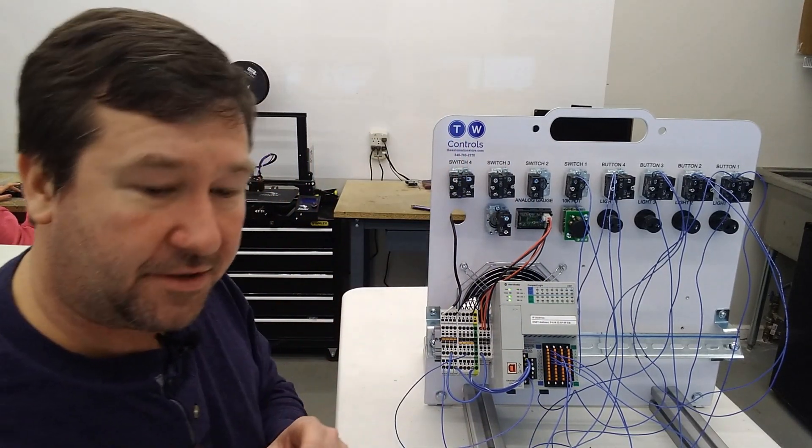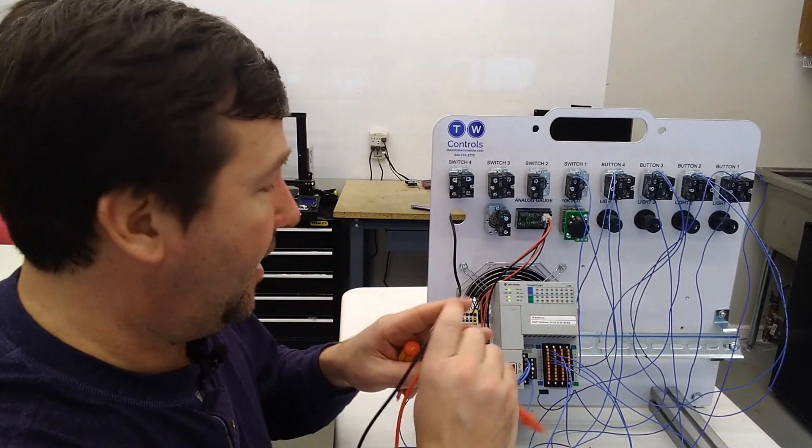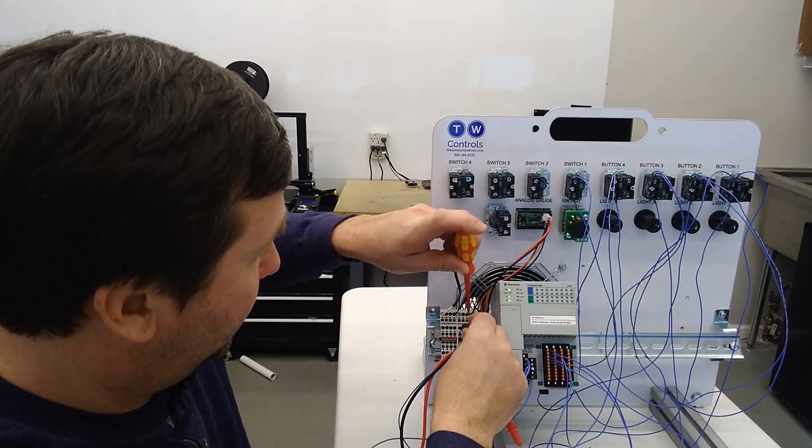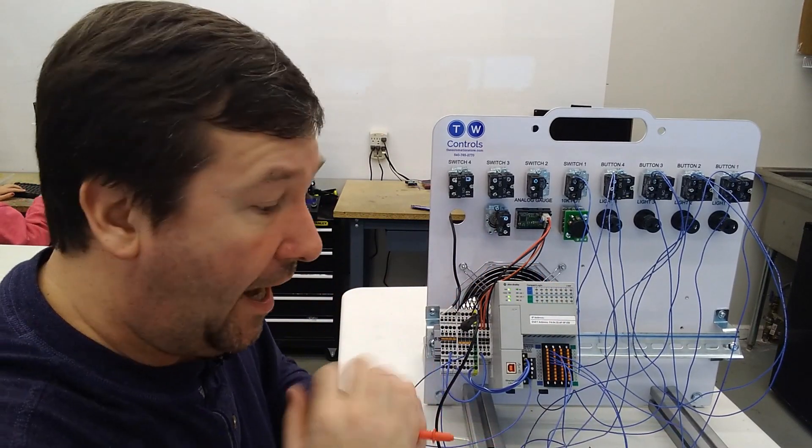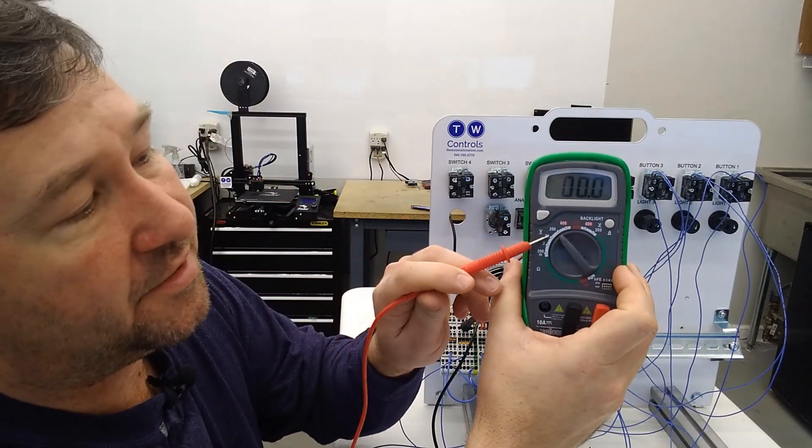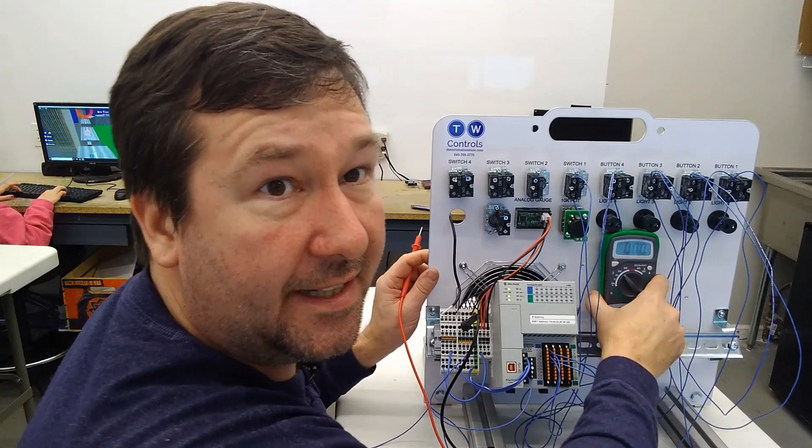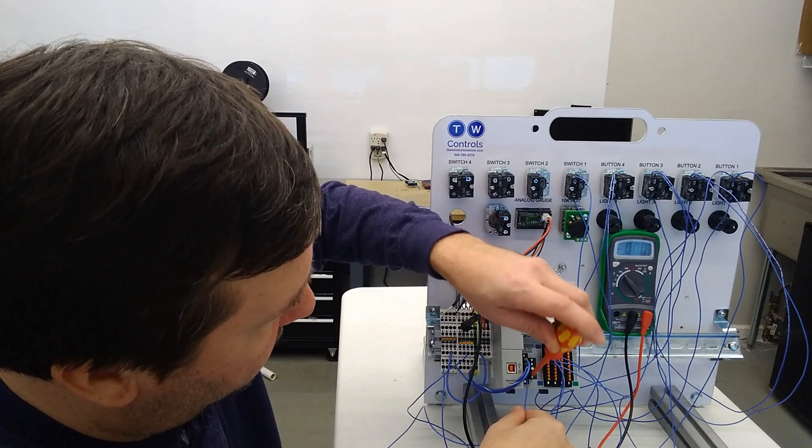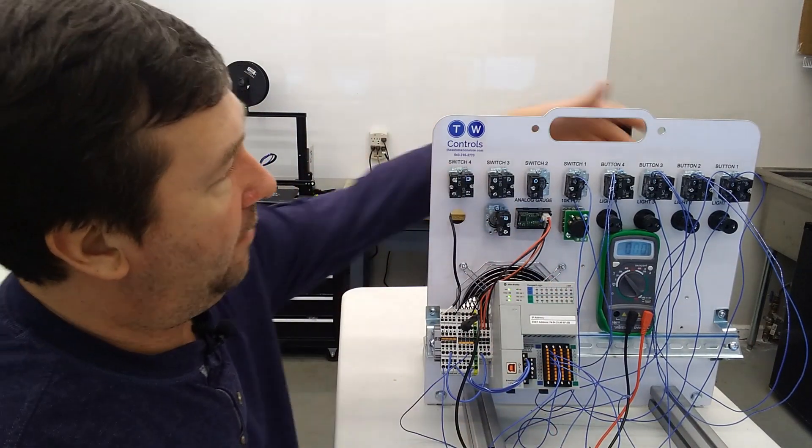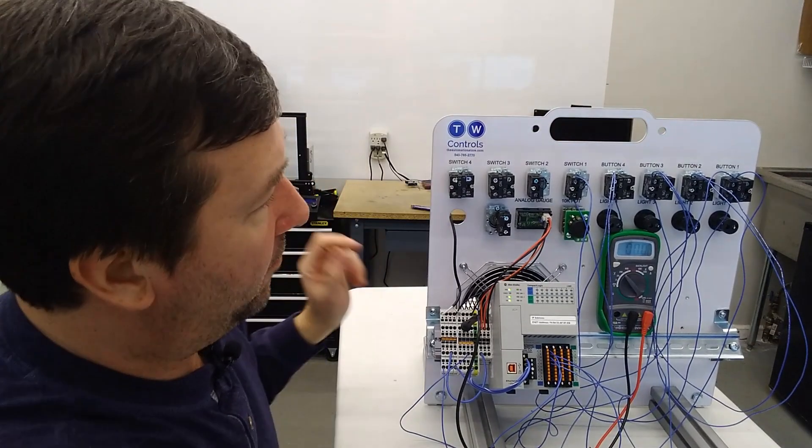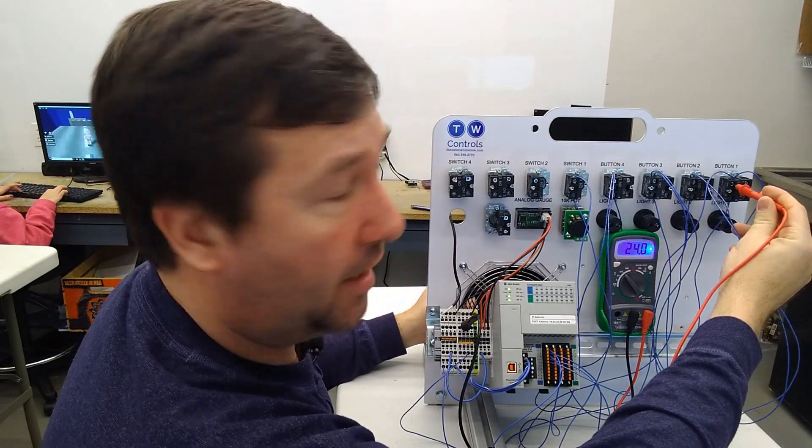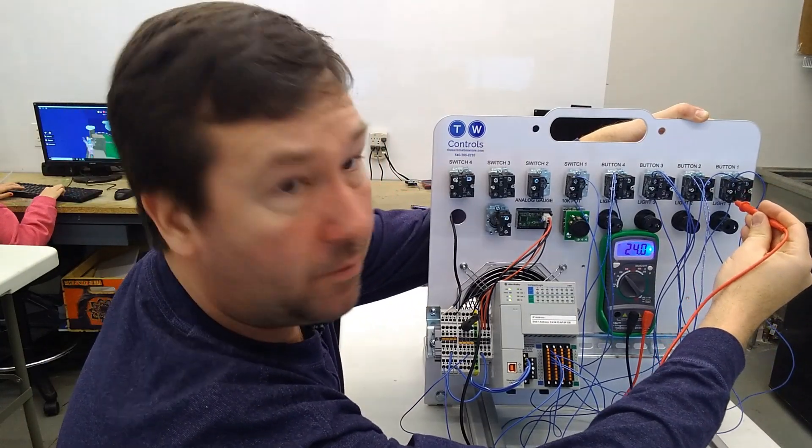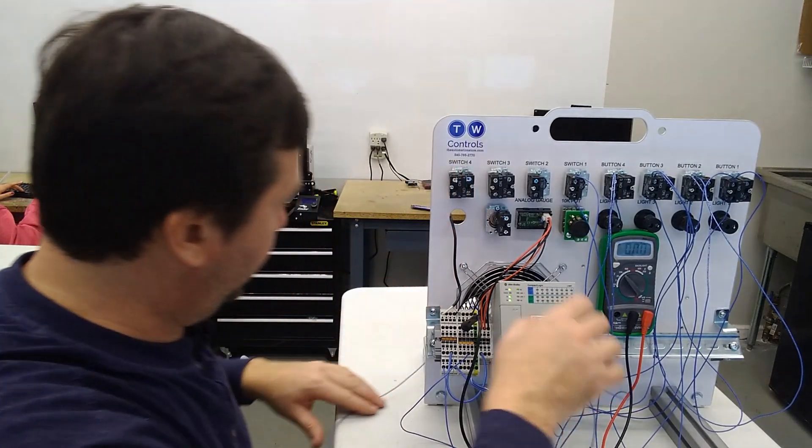The one that I really think you'll probably forget is this FP minus terminal. And let's just do an exercise to see how we can figure that out. Because I'll show you how easy it is to think that you have it wired right. So I'm going to just connect the minus of my voltmeter to one of my minus terminals, which would be typically how I really do troubleshoot. And then I'm going to set my voltmeter to DC volts. And we're going to take this FP minus terminal off again. Now, when we press our buttons, none of them work. But when we go to test here, we have 24 volt at the top of our contact. We also have 24 volt when we press our contact.